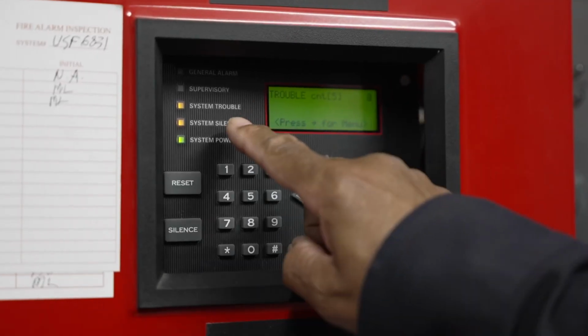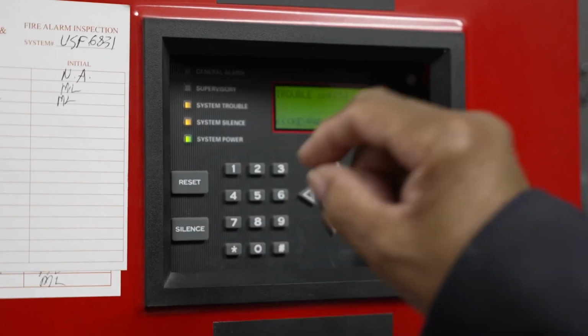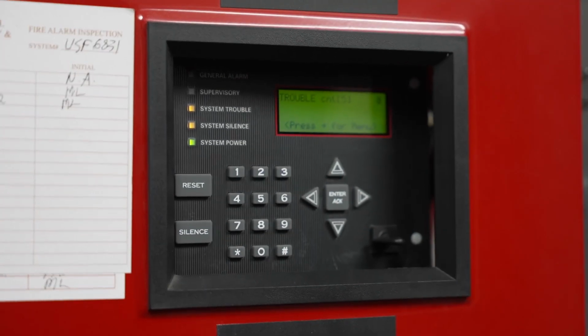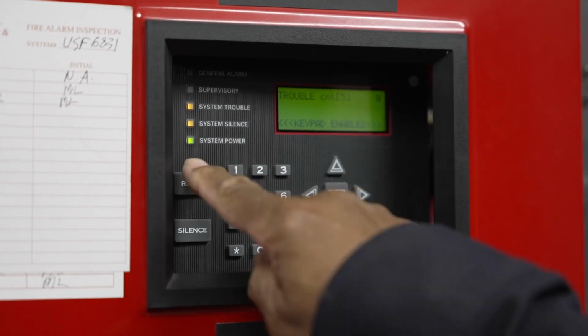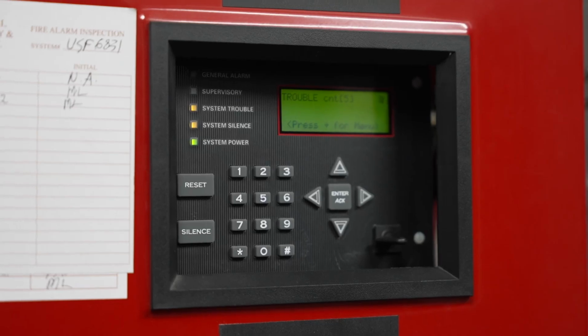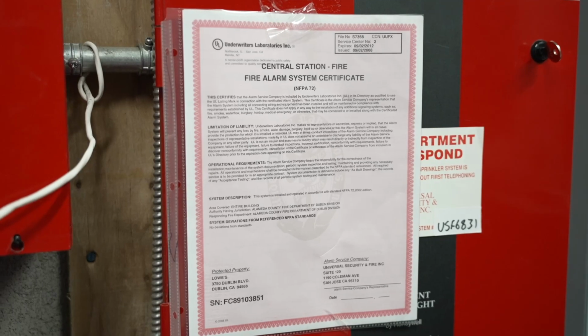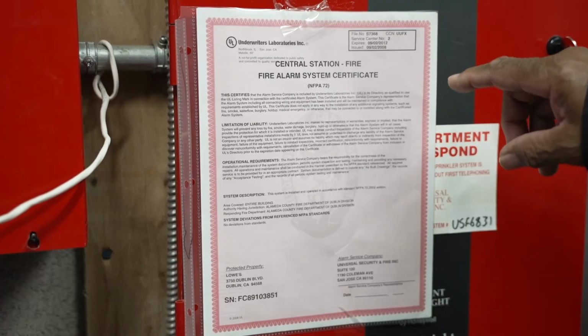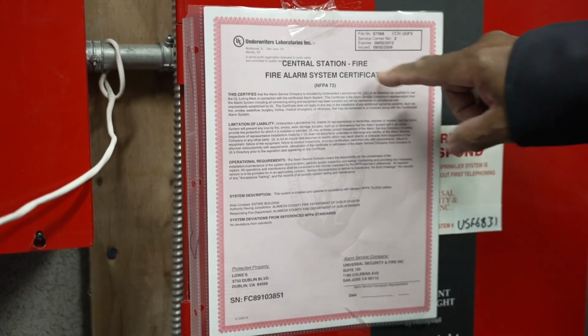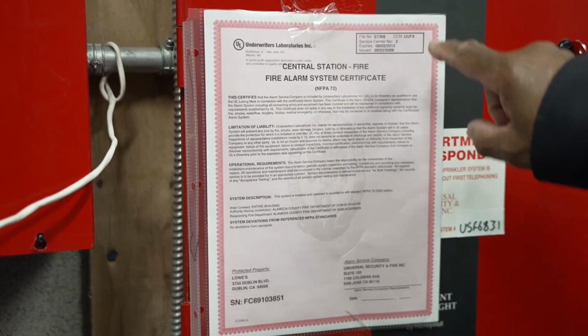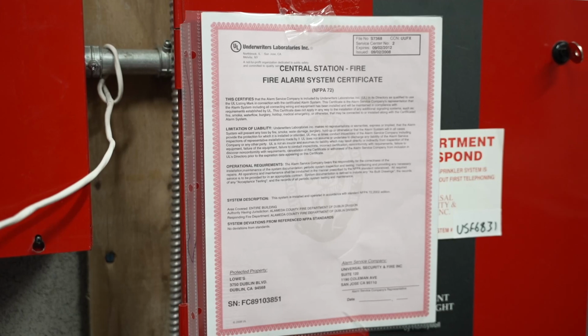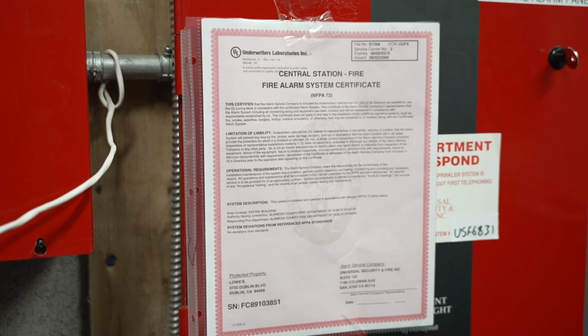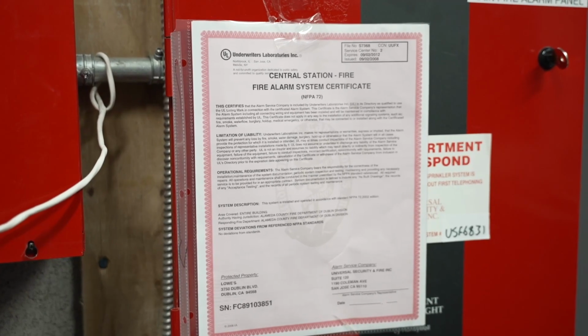As you can see, we have system trouble and we have system silence. This will require a fire alarm tech to come out and restore the system to green, which is the way it should be. Full fire alarm systems have what's called the Fire Alarm System Certificate from Underwriters Laboratories. These are dated. They are not necessarily required, but many of the larger corporations require their stores to have these.